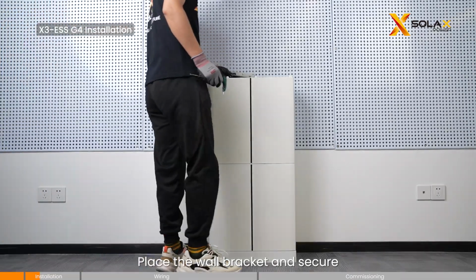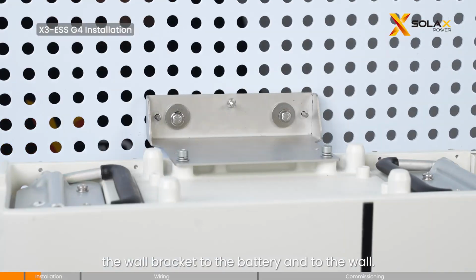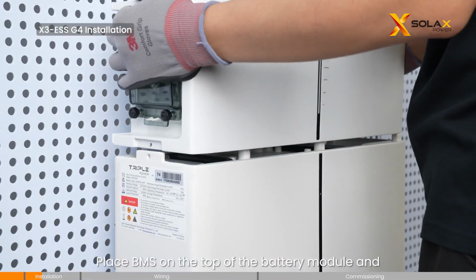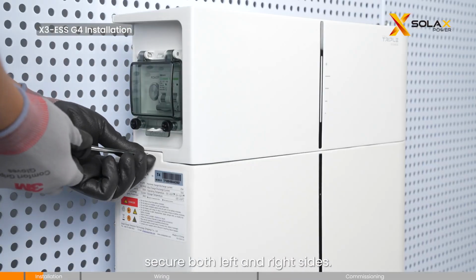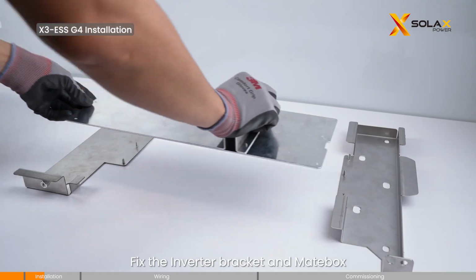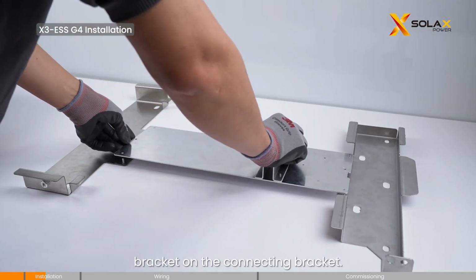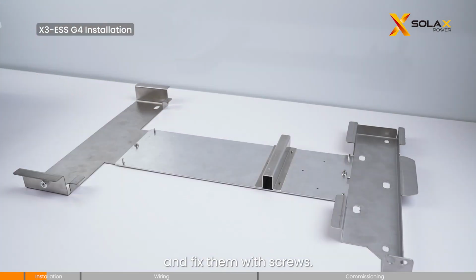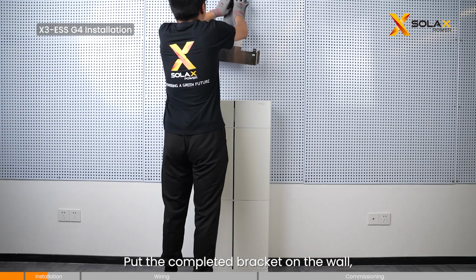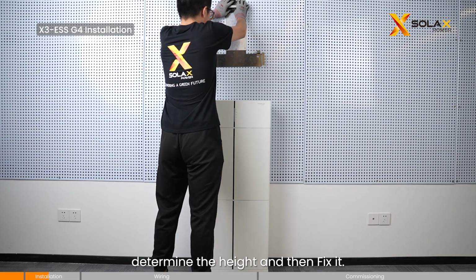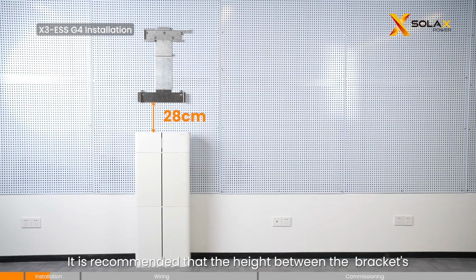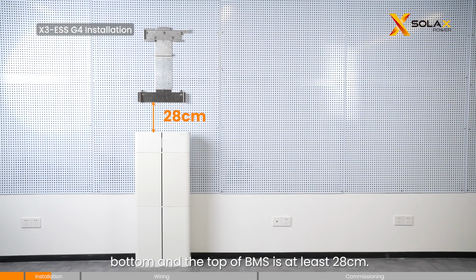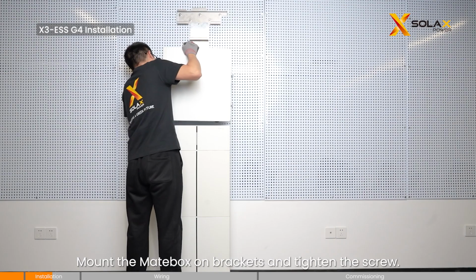Place the wall bracket and secure the wall bracket to the battery and to the wall. Place BMS on the top of the battery module and secure both left and right sides. Fix the inverter bracket and matebox bracket on the connecting bracket and fix them with screws. Put the completed bracket on the wall, determine the height and then fix it. It is recommended that the height between the bracket's bottom and the top of BMS is at least 28 centimeters. Mount the matebox on brackets and tighten the screw.